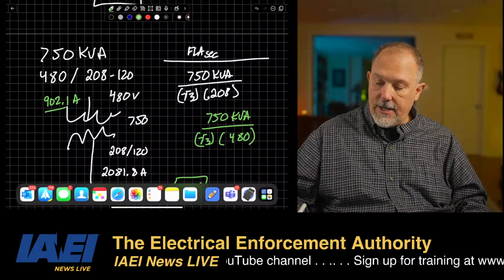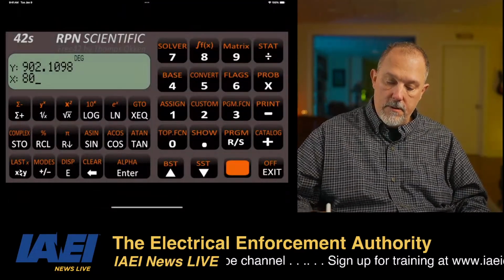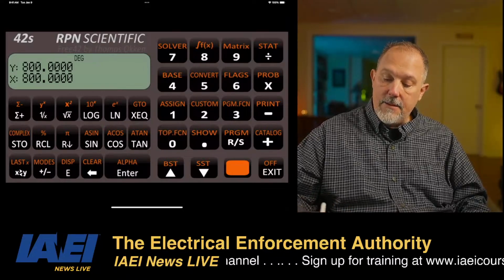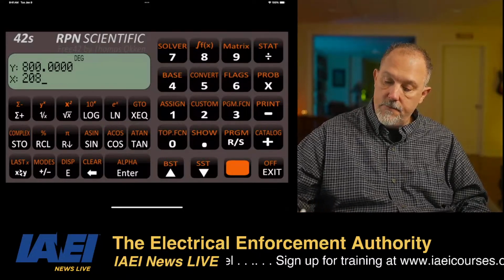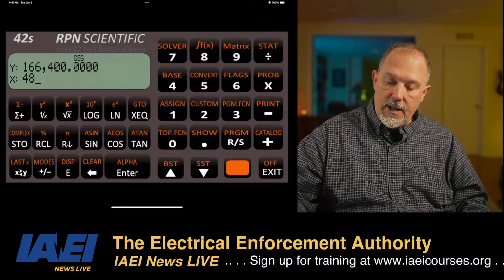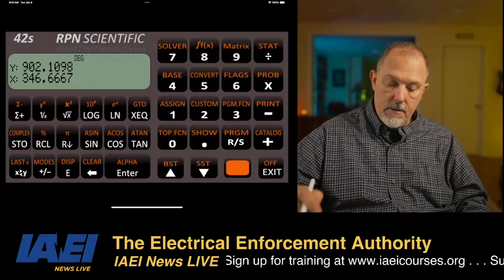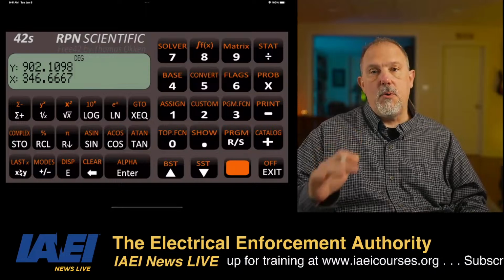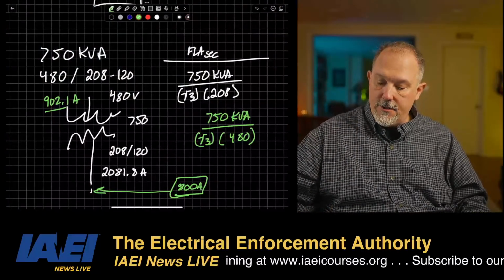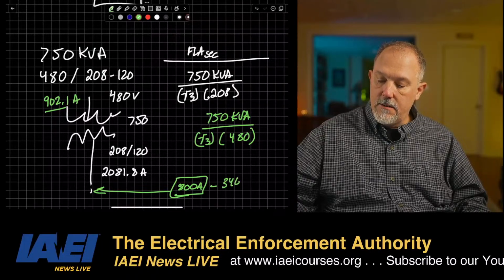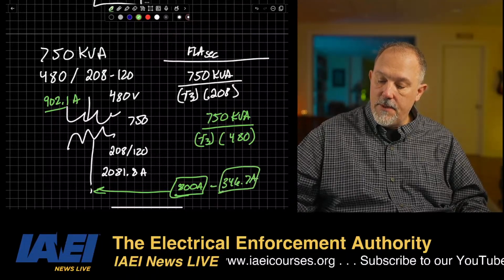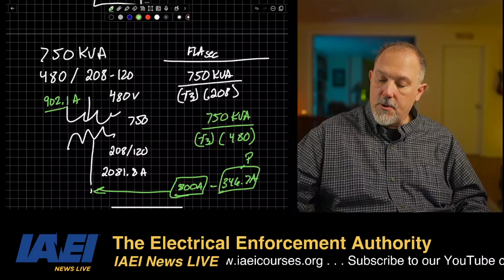I would take 800 times 208, divide that by 480, 346.7. That would mean I have 346.7 amps on the primary.